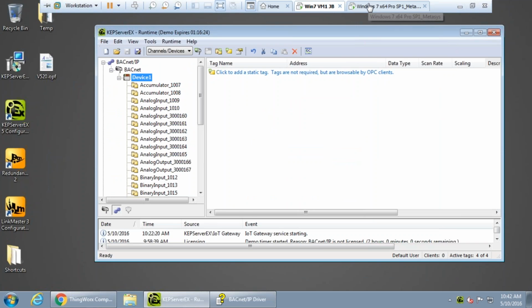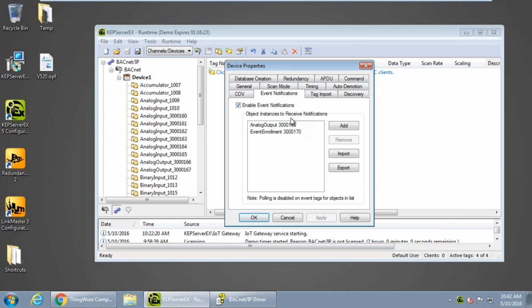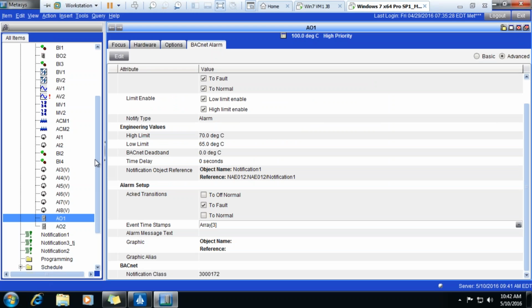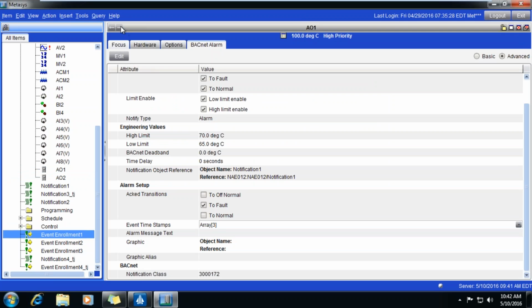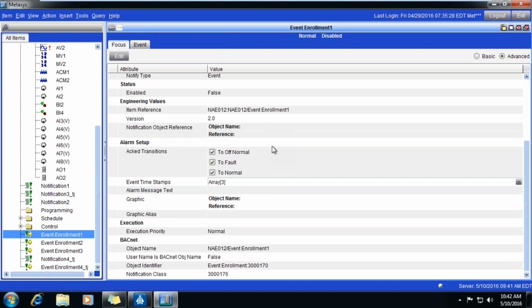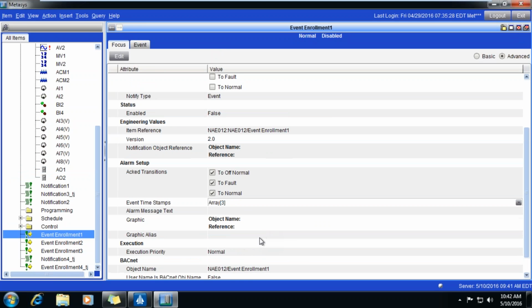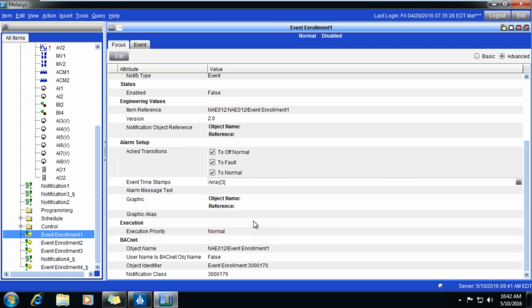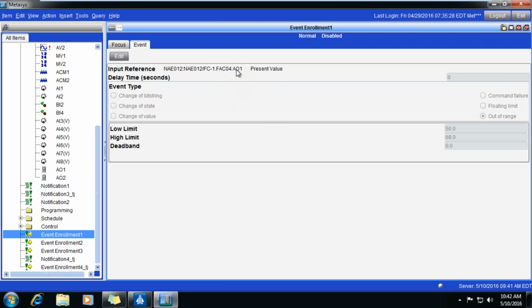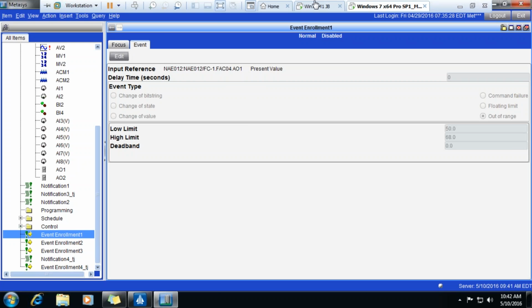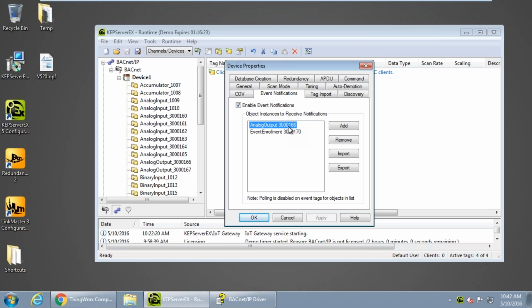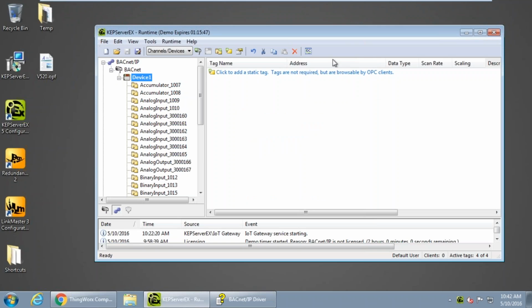For this alarm list, if you're using algorithmic alarms, which are set up in event enrollment objects, you'll want to add the event enrollment object to this list as well as the object it's alarming on. For example, my event enrollment object alarm is alarming off the value of analog output, so to catch this algorithmic alarm, I need to add analog output to the list along with the event enrollment object.